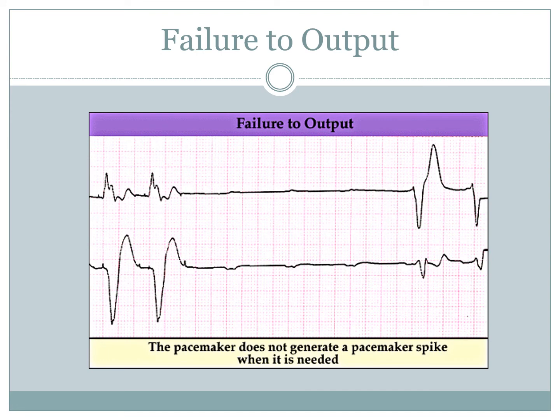A third type of failure can be simply a failure to output. This is when the pacemaker does not generate an impulse or pacemaker spike when it is needed. So clearly, looking at the top one first, there's this long pause. That's when the heart is not beating. There's nothing going on there. Clearly the pacemaker should fire, and it does not. And so that can be failure to output, and certainly that pacemaker is no longer functioning.